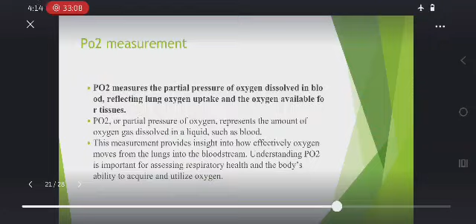What is PO2? PO2 means partial pressure of oxygen. It is used to measure how much oxygen is present as oxygen gas dissolved in a liquid such as blood. PO2 measurement: partial pressure of oxygen in blood is measured by an O2 electrode to determine oxygen content. The PO2 electrode means the Clark electrode, which measures the current that flows when constant voltage is applied to the system. As dissolved O2 diffuses from the blood, a change in current occurs, which gives the PO2 measurement. The PO2 normal value is 13.3 kilopascal.